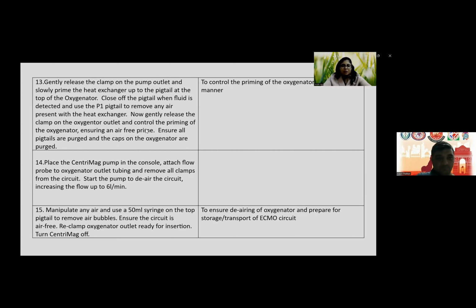Now gently release the clamp on the oxygenator outlet and control the priming of the oxygenator, ensuring an air-free prime. You ensure all pigtails are purged and the caps on the oxygenator are also purged, right? So this is done to control the priming of the oxygenator in an air-free manner. You place the CentriMag pump in the console. Since they were using the CentriMag pump, it can be any pump. So you place the pump in the console, attach the flow probe to the oxygenator outlet tubing and remove all the clamps from the circuit.